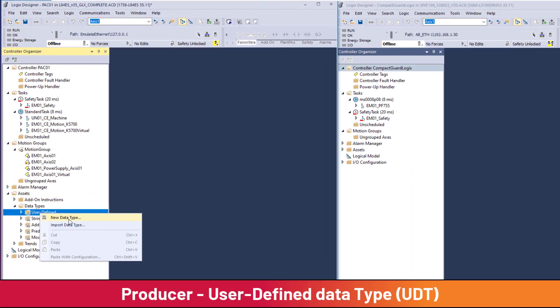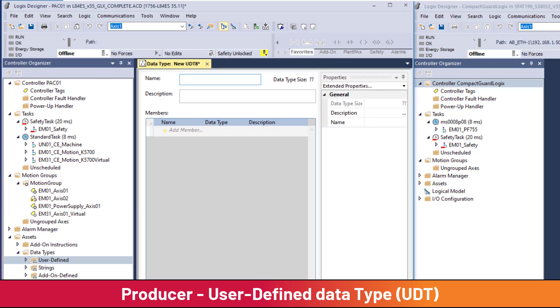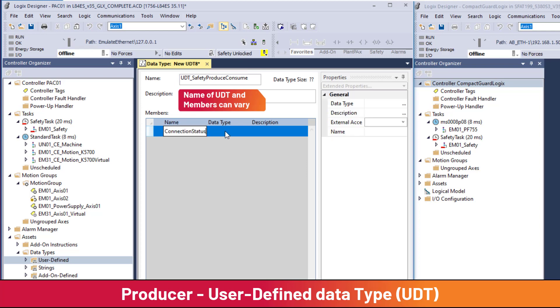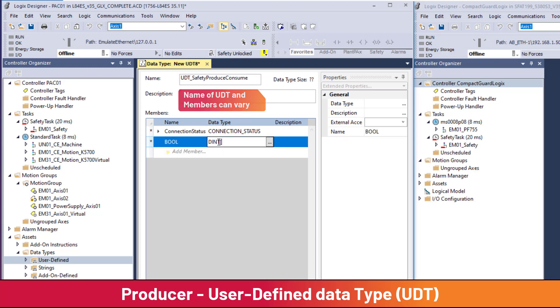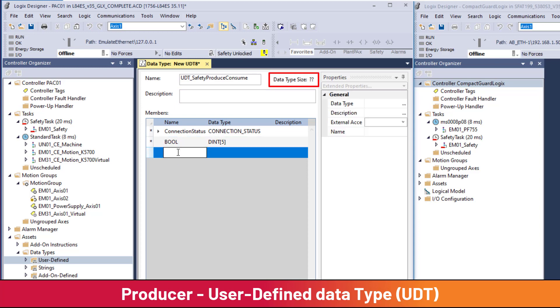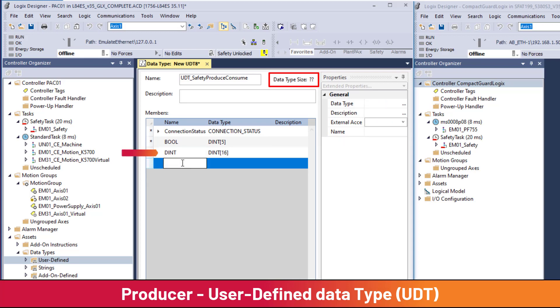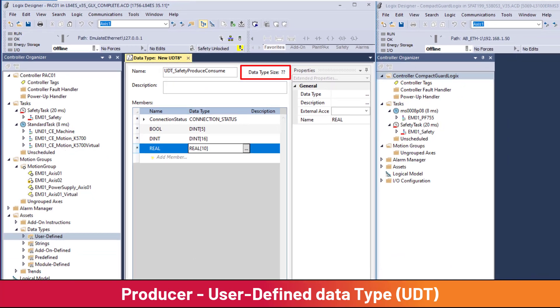A user-defined data type for the produce/consume connection must be created. The user-defined data type will be named UDT_safety_produce_consume. The first member of the UDT must be data type Connection Status, which contains Run Mode and Connection Faulted. The UDT has a maximum size of 128 bytes. Here, the UDT is fully loaded with 5 double integers for booleans, 16 double integers for integers, and 10 reals.